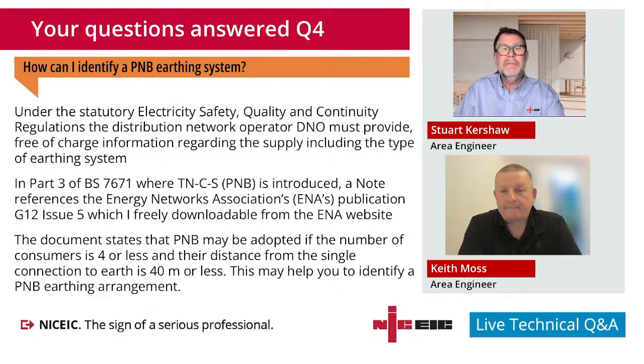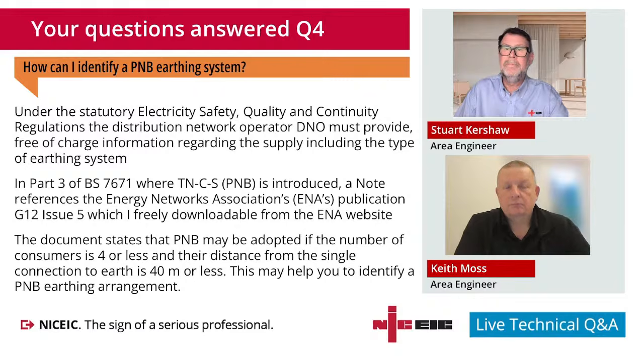Yeah. You know, if there's an earth terminal provided by the DNO, then it's their duty to maintain that, under the ESQCR regulations. It's always been the case. Yeah, absolutely. And if somebody is considering installing that additional earth electrode, then our advice is strongly to have that conversation with the DNO, because they might not actually want you to have any input into their earthing arrangement, because, like you say, they have to maintain it based on that statutory requirement in the ESQCR regs. So it is their responsibility.